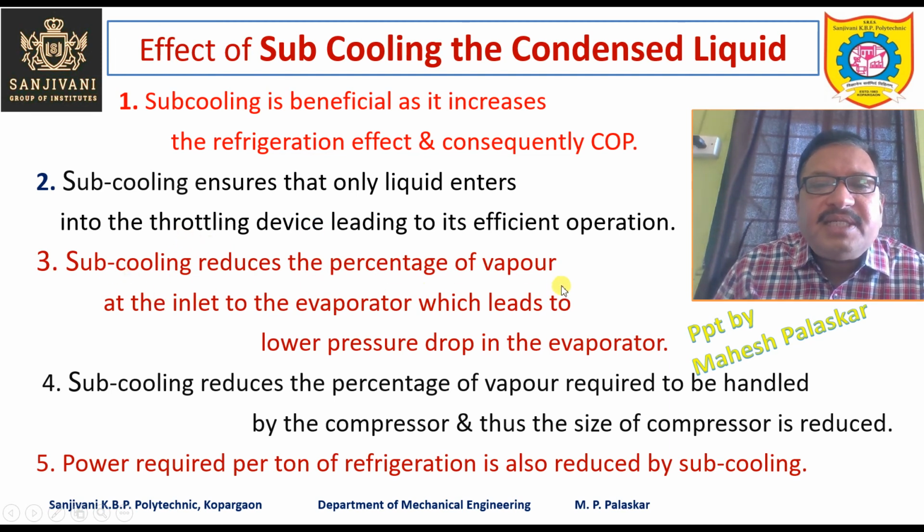Subcooling reduces the percentage of vapor at the inlet to the evaporator. The percentage of the vapor which is entering the evaporator will be reduced and the percentage of liquid will be increased, and that will lead to lower pressure drop in the evaporator.